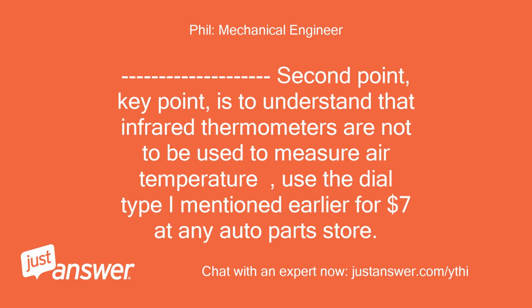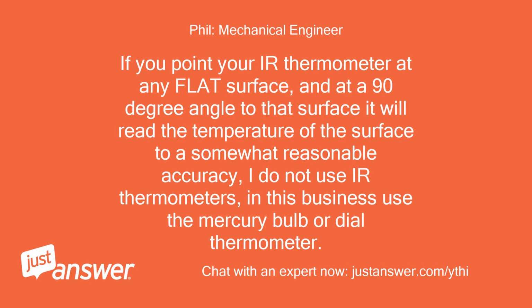Second point, key point, is to understand that infrared thermometers are not to be used to measure air temperature. Use the dial type I mentioned earlier for $7 at any auto parts store. If you point your IR thermometer at any flat surface, and at a 90-degree angle to that surface, it will read the temperature of the surface to a somewhat reasonable accuracy. I do not use IR thermometers. In this business, use the mercury bulb or dial thermometer.